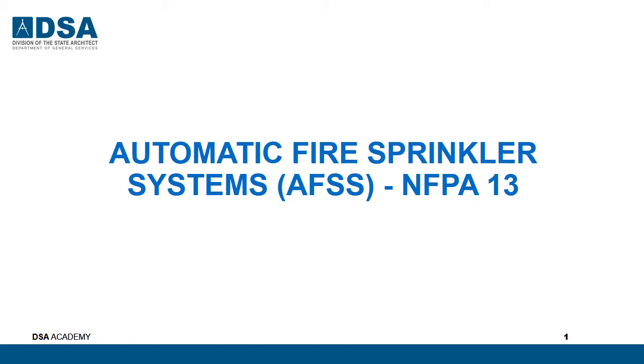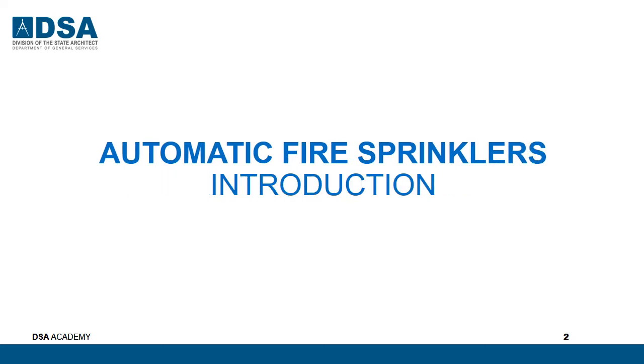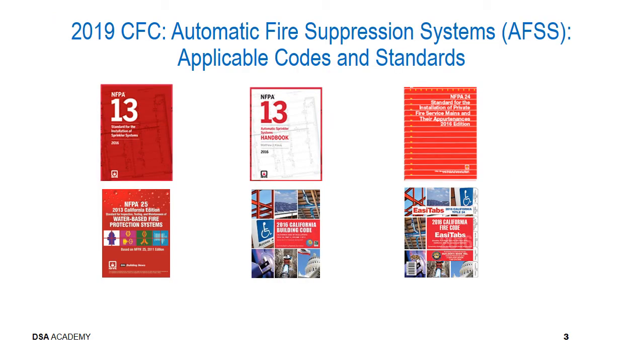Automatic fire suppression systems, NFPA 13. Automatic fire sprinklers. Introduction. The 2019 California Fire Code and Building Code adopt the 2016 edition of NFPA 13. Other applicable standards will be NFPA 24 for the installation of the private fire service main and any of the appurtenances thereto, such as post indicator valves and fire department connections.